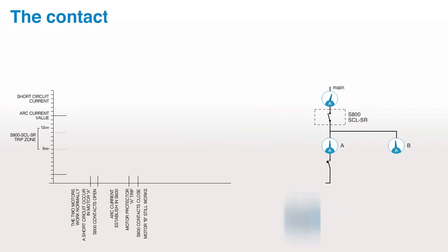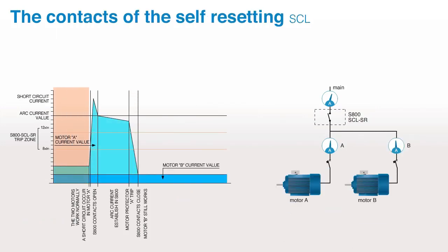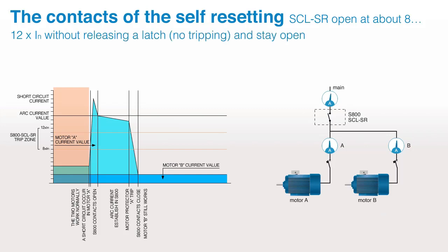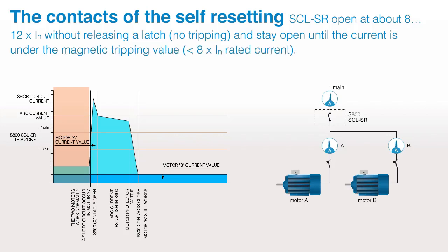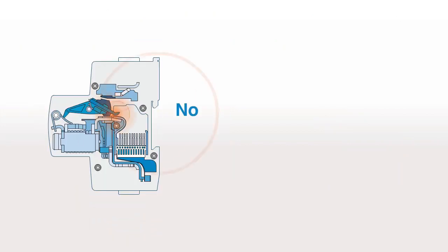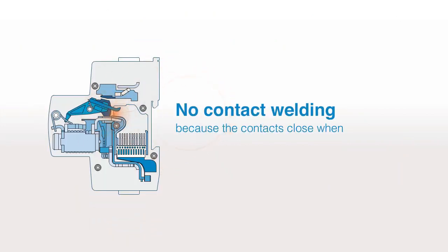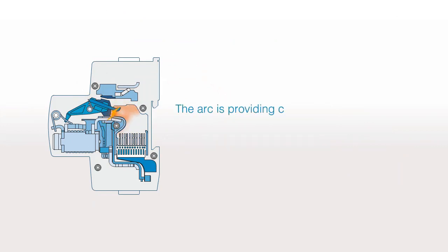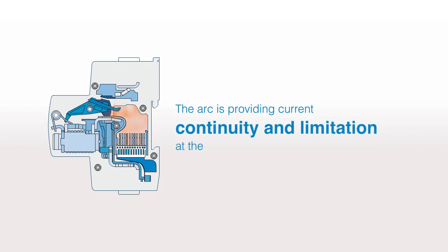The contacts of the self-resetting SCL SR open at about 8 to 12 times rated current without releasing the latch, no tripping, and stay open until the current is under the magnetic tripping value, less than 8 times rated current. No contact welding, because the contacts close when the short circuit current is small enough. The arc is providing current continuity and limitation at the same time.